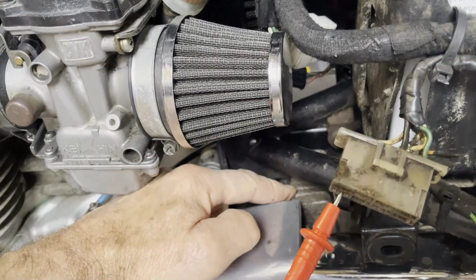But it is possible to test in here. So these white cables, which actually come via the harness down past your chain, in behind this cover and into your alternator, you can probe in here with your multimeter, which in this instance I've set to the 200 ohms range, that being the lowest range, because what we're going to be talking about here are very low readings.